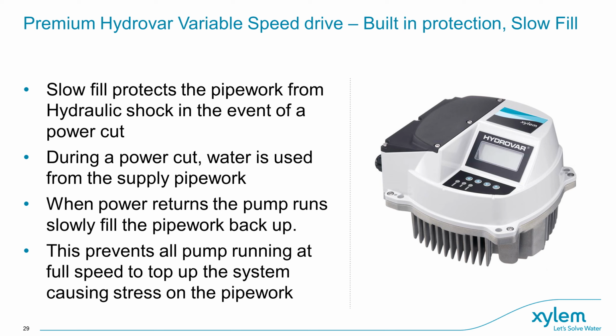The GHVR booster set and Hydrovar also come with a slow fill mode, which protects the pipework from hydraulic shock in the event of a power cut. During a power cut, water could be taken from the pipework but not replaced by the booster set. Once power is restored, the drives may see a sudden drop in pressure and start all pumps on the set to replenish the line. However, this sudden rush of pressure can cause water hammer or damage the pipework, leading to a burst. The Hydrovars can be programmed so that in the case of a power cut, they run at a slower setting for a short time before switching back to the original set point.